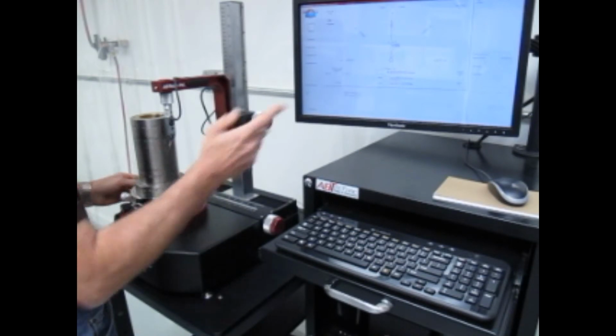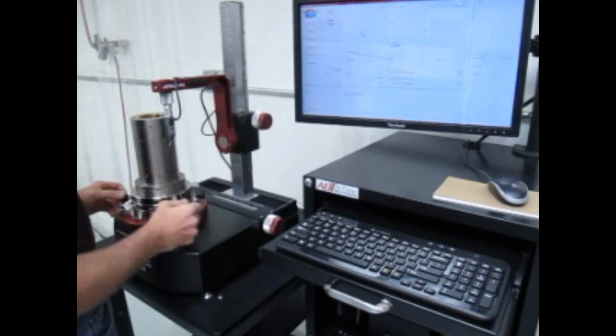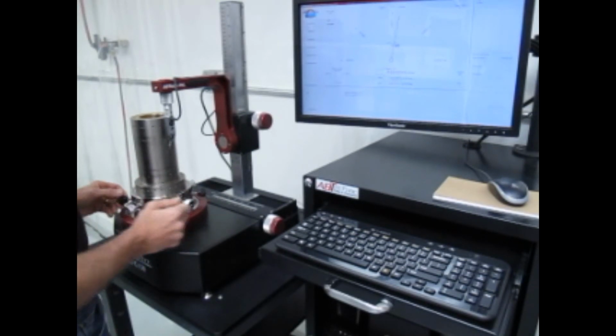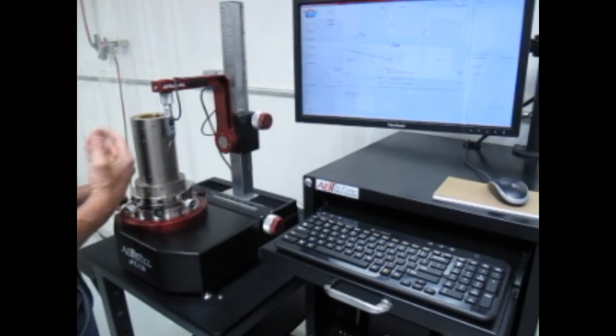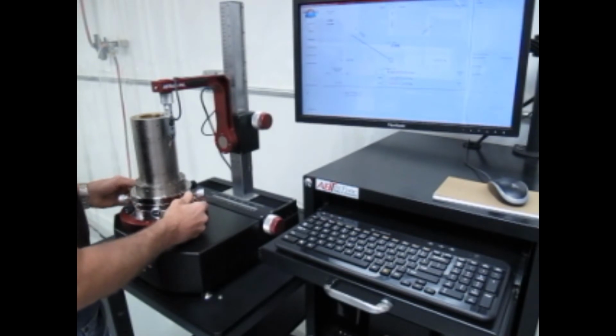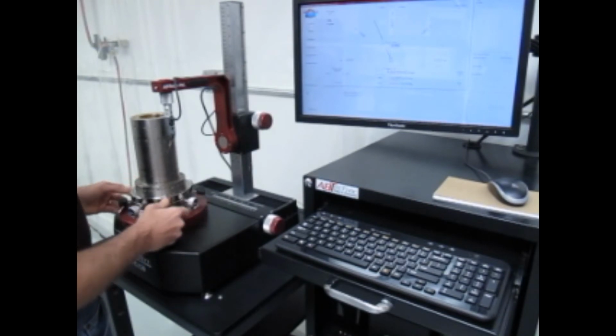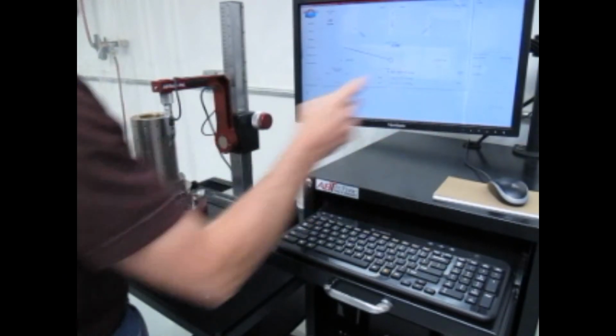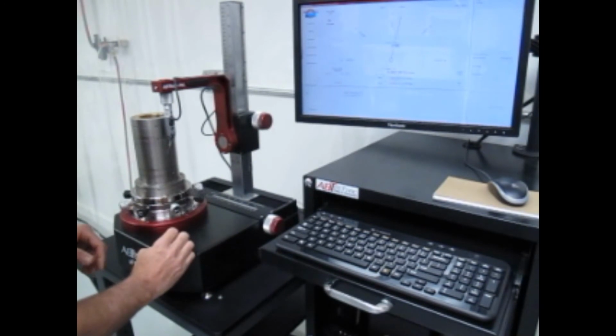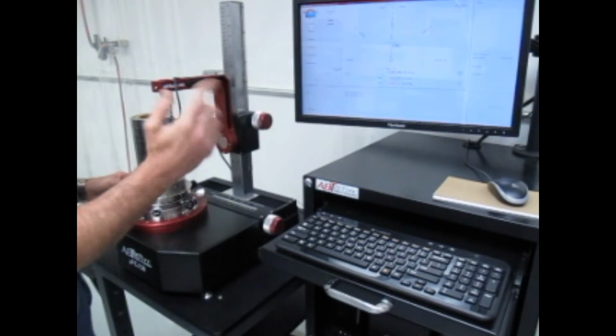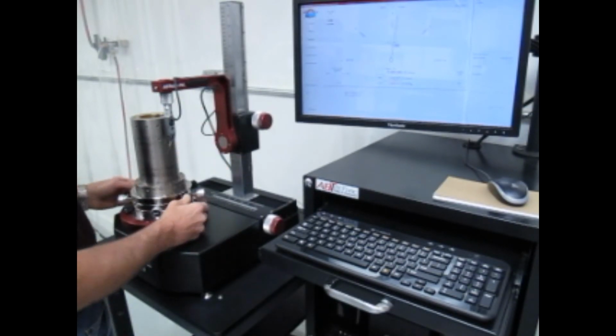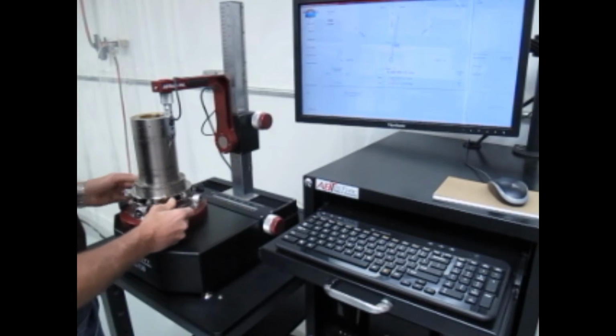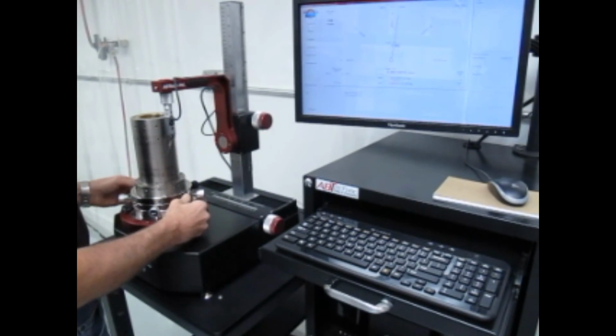And you can see that the needle stays on scale the whole time and the digital readout does not turn red. So I'm now on scale, and essentially I can take a measurement now. I do want to, or I can in some cases, and I do want to now fine-tune that so that I can bring it in better alignment to the rotary axis. Right now I am 9 thousandths, almost 10 thousandths, which is nearly the full displacement of the probe, plus or minus 10 thousandths. So I've got 9 thousandths of TIR, so I'm going to find my max and the nearest black knob right in line with that.